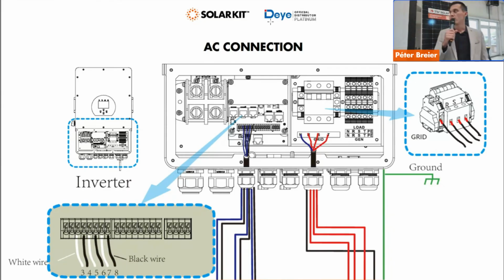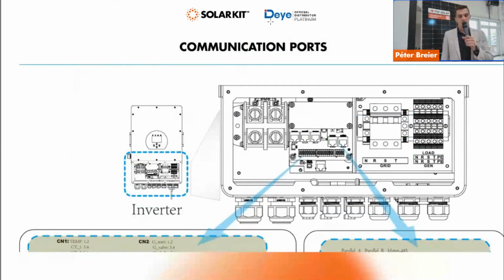Here also there is a highlighted area which shows you the connection of the CT wires. It's very important that you go from white to black on all three CTs, and also that you leave empty the first two pins of these communication terminals, because they are for a battery thermostat. Basically, you get a device which can measure the temperature of the batteries. If you are, for example, using a lead-acid battery, you put it in the middle of the battery, because that part will be heated the most, and then you connect it to the first two pins here. So if the inverter gets the data that the batteries are very high in temperature, it will shut down the battery port.